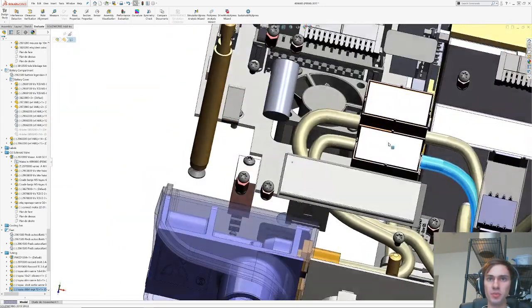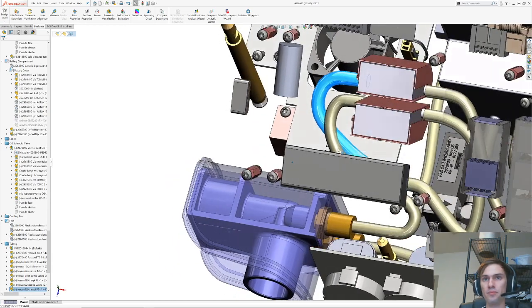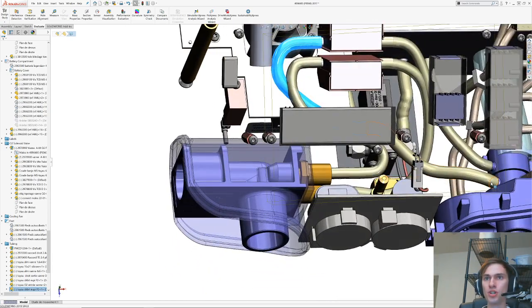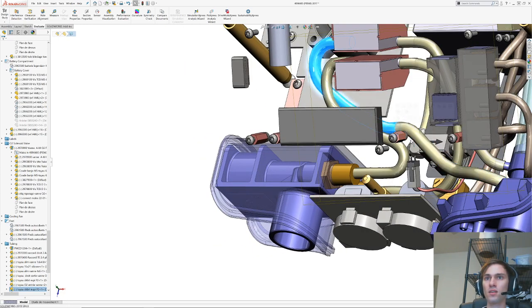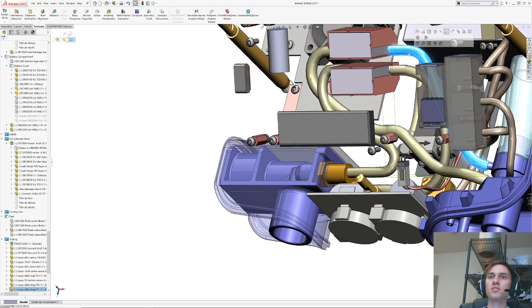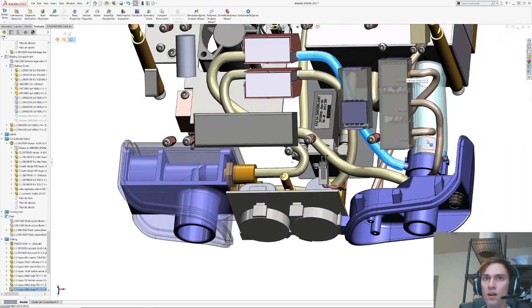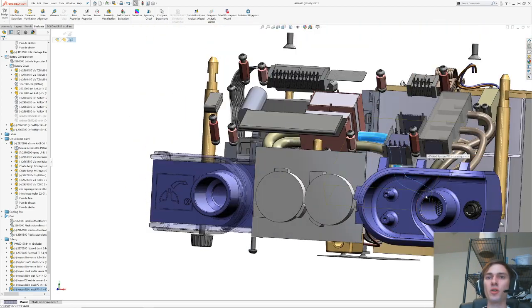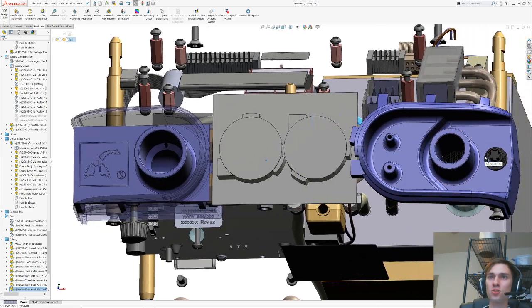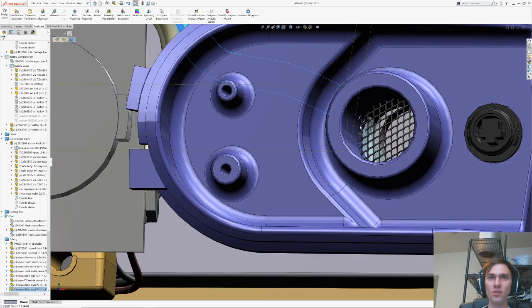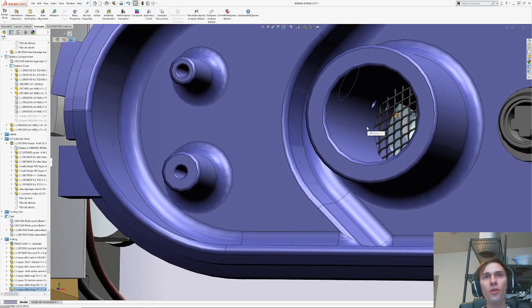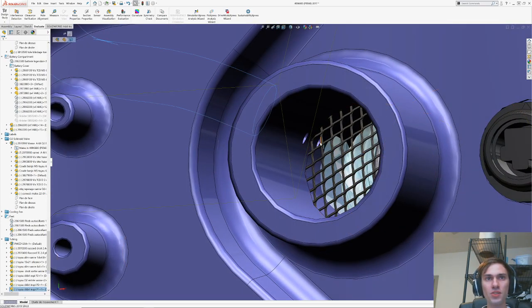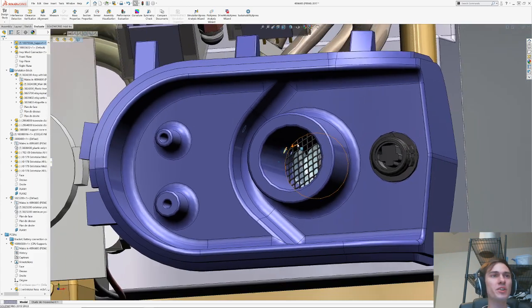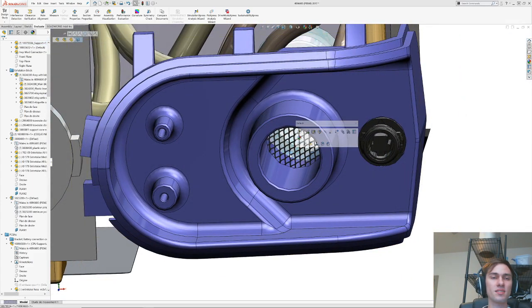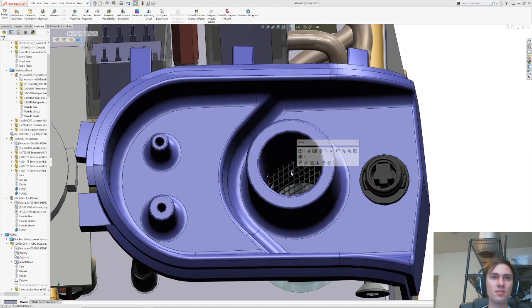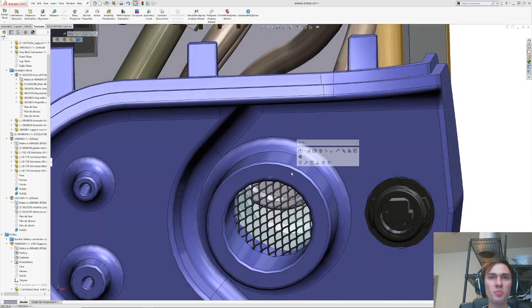And then this delta P sensor up here is measuring the difference between the pressure to the lungs, which is this tube here, pressure in the lung, and this tube. Oh, weird. I bet this is like another pitot tube assembly, right? So I bet we'll find that one is facing that tube and one is orthogonal to the tube. So there's the orthogonal one. Oh no, that's weird. Look, they're both orthogonal to the direction of flow. So why are they measuring the delta P across this? They're measuring the delta P across this screen. Why are they measuring the delta P across the screen?